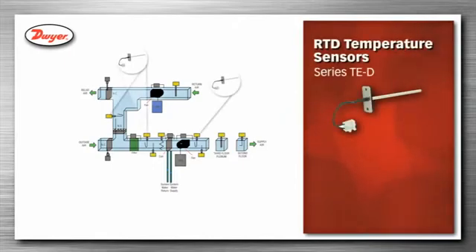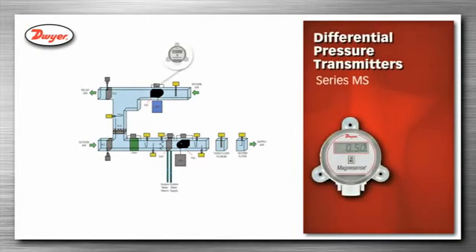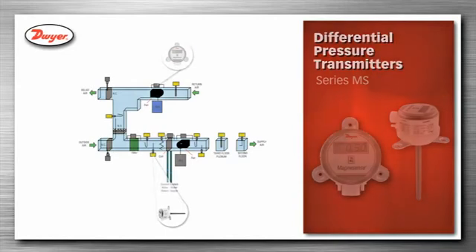Temperature sensors, series TE-D RTD temperature sensors, and series TE-A averaging RTD temperature sensors, are inserted into the duct and used to monitor the supply air, mixed air, and exhaust air temperatures. Differential pressure transmitters, series MS, are used with a static pressure sensor or with an inherent static probe to monitor discharge air and mixing air duct static pressures.